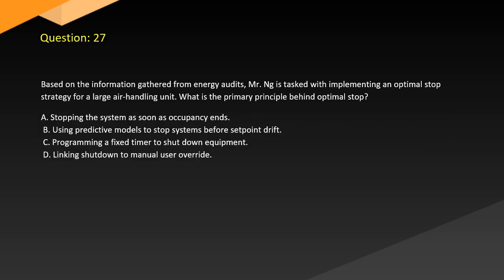Question 27. Based on the information gathered from energy audits, the facilities team is tasked with implementing an optimal stop strategy for a large air handling unit. What is the primary principle behind optimal stop? A. Stopping the system as soon as occupancy ends. B. Using predictive models to stop systems before setpoint drift. C. Programming a fixed timer to shut down equipment. D. Linking shutdown to manual user override.